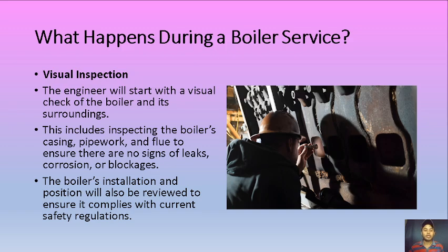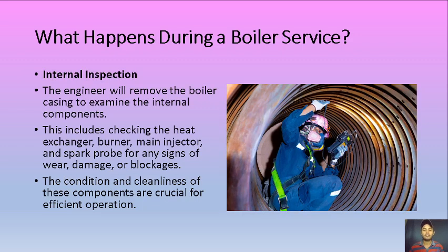So for visual inspection, the engineer will start with a visual check of the boiler and its surroundings. This includes inspecting the boiler's casing, pipework, and flue to ensure there are no signs of leaks, corrosion, or blockages. The boiler's installation and position will also be reviewed to ensure it complies with current safety regulations. For internal inspection, the engineer will remove the boiler casing to examine the internal components. We don't do this every day. We do have scheduled maintenance for this one. This includes checking the heat exchanger, burner, main injector, and spark probe for any signs of wear, damage, or blockages. The condition and cleanliness of these components are crucial for efficient operation.